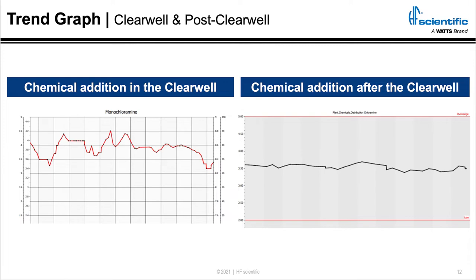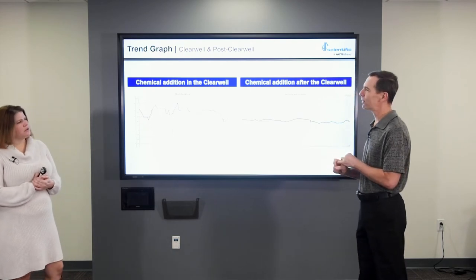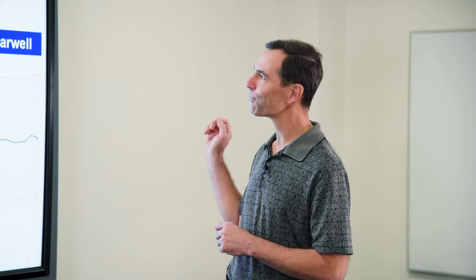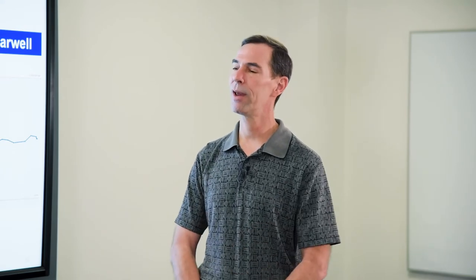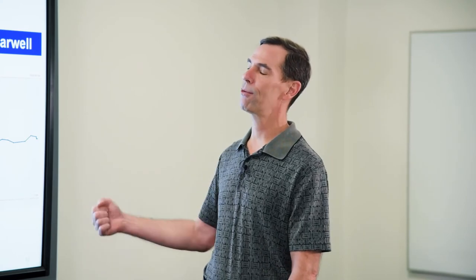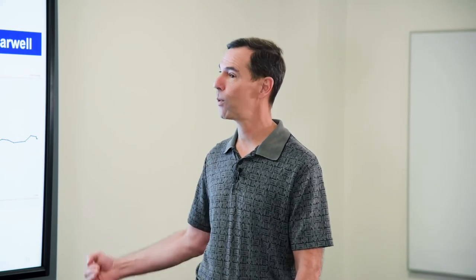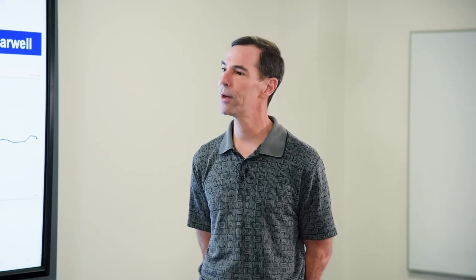The post-clear well plant was within about 0.2 ppm — very little fluctuation over the course of 24 hours. There's one more nice additional perk of out-of-clear well chloramination: should you have a plant upset that affected the chemical feeds, say a loss of your chlorination system, rather than having hundreds of thousands or millions of gallons of bad water in your clear well that you don't have a good way of dealing with, if your chemical additions are being done as you're drawing the water out of that clear well, you can hit it with chemistry right there and rapidly fix your problem in a much more effective way than having to dump and retreat a million-gallon clear well.